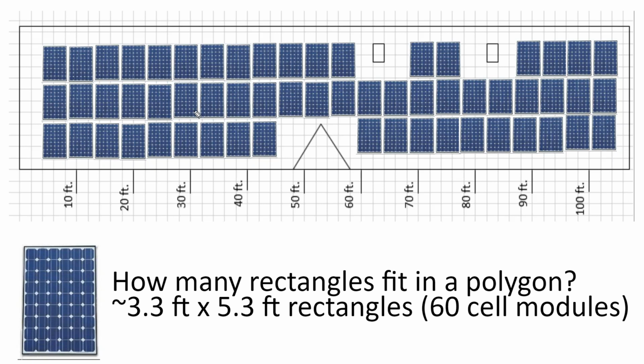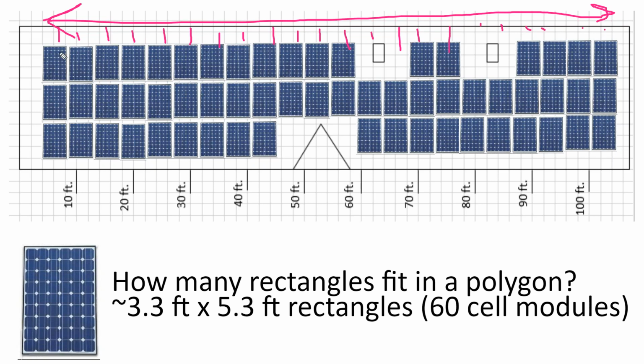So what that means is, if we see that microinverter circuits can only accept 16 modules, you might look at your array layout and count: 1 through 16, then 17 through 22. So this array is 22 modules long, and you get into circuit design.